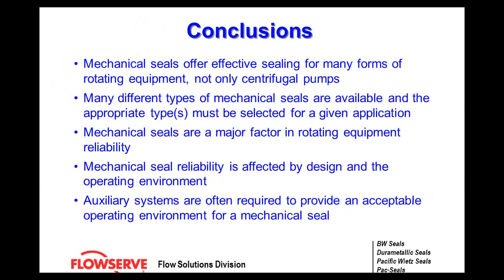In conclusion, mechanical seals can offer effective sealing for many forms of rotating equipment — not only centrifugal pumps, but also steam turbines, compressors, vessels, and mixing shafts. Many different types are available and must be selected for the given application. Depending on what you're pumping, mixing, or driving, you need to ensure you have the right metallurgy, proper balance profile for proper lubrication, and proper selection of the seal flush — all addressed by the application engineer.